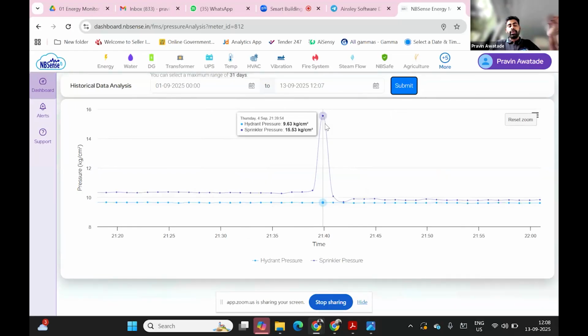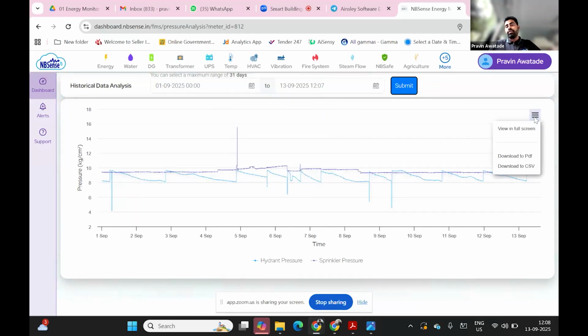This was one incident recorded on 4th September at around 9:40 p.m. evening time. Your hydrant pressure and sprinkler pressure go very high. Most probably the pump got operated. If you want to download this data in any format for further analysis, you can export it in CSV, PDF, or Excel format.